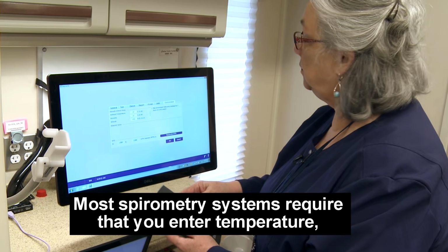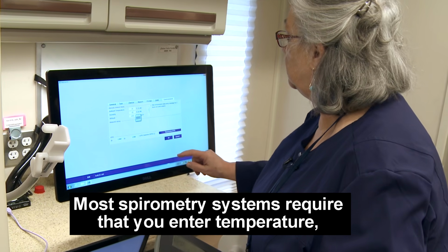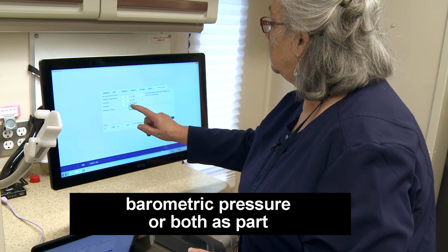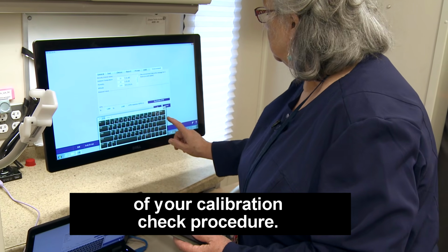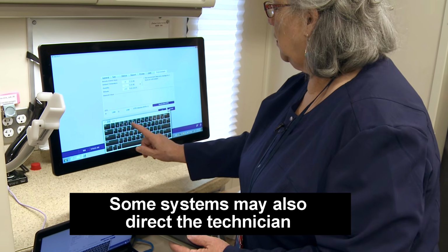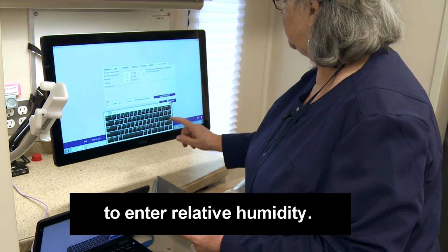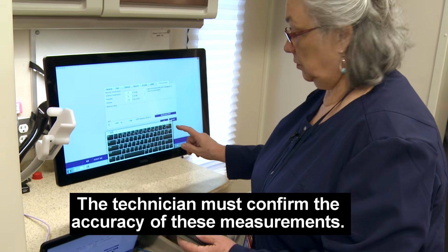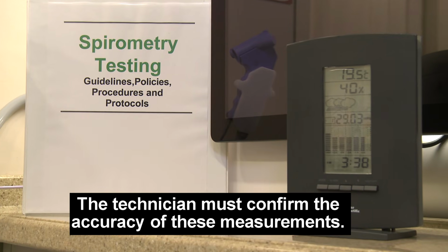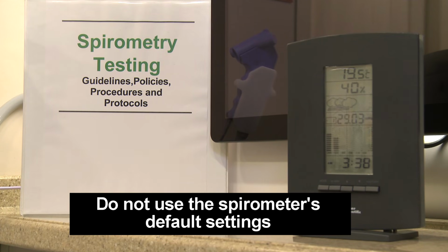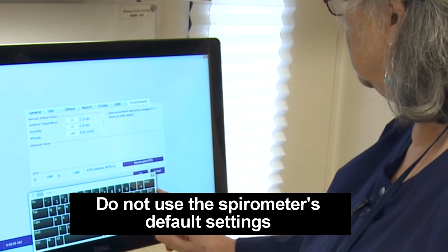Most spirometry systems require that you enter temperature, barometric pressure, or both as part of your calibration check procedure. Some systems may also direct the technician to enter relative humidity. The technician must confirm the accuracy of these measurements. Do not use the spirometer's default settings for ambient conditions.